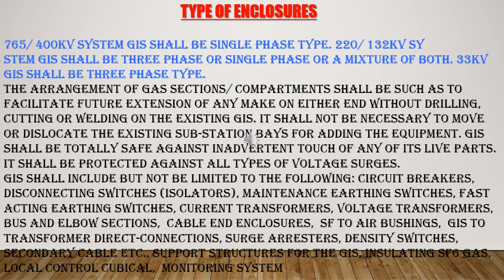The arrangement of compartments shall be such as to facilitate future extension of any make on either end without drilling, cutting or welding on the existing GIS. It shall not be necessary to move or dislocate the existing sub-station bays for adding the equipment. GIS shall prevent inadvertent touch of any of its live parts.